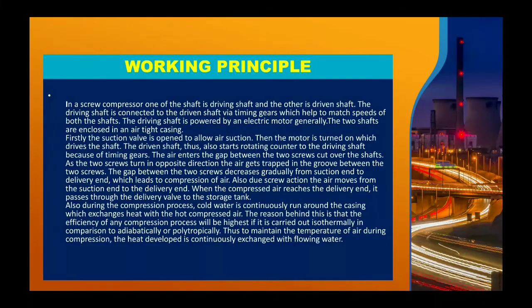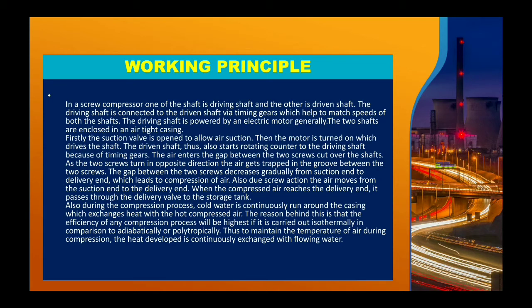First, the suction valve is opened to allow air suction. Then the motor is turned on, which drives the shaft. The driven shaft also starts rotating counter to the driving shaft because of the timing gear. Air enters the gap between the two screws over the shaft. As the two screws turn in opposite directions, the air gets trapped in the groove between them. The gap between the two screws decreases gradually from the suction end to the delivery end.